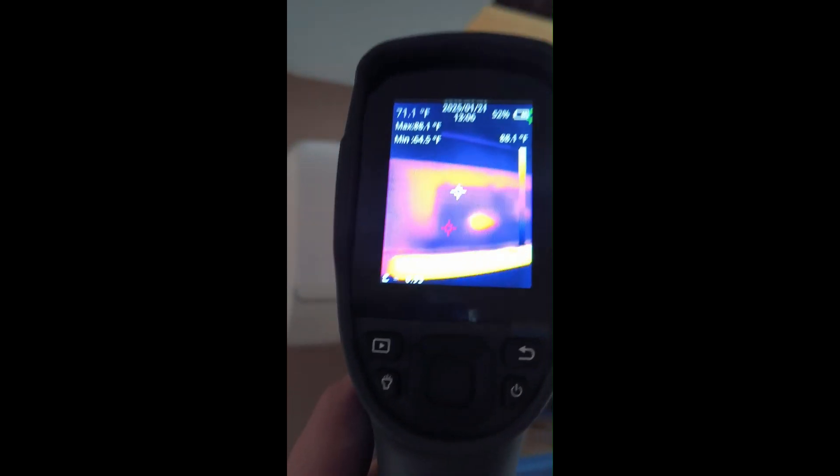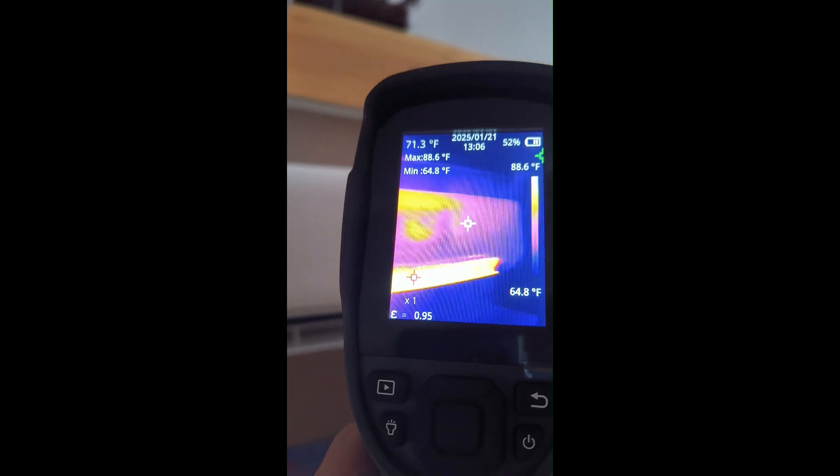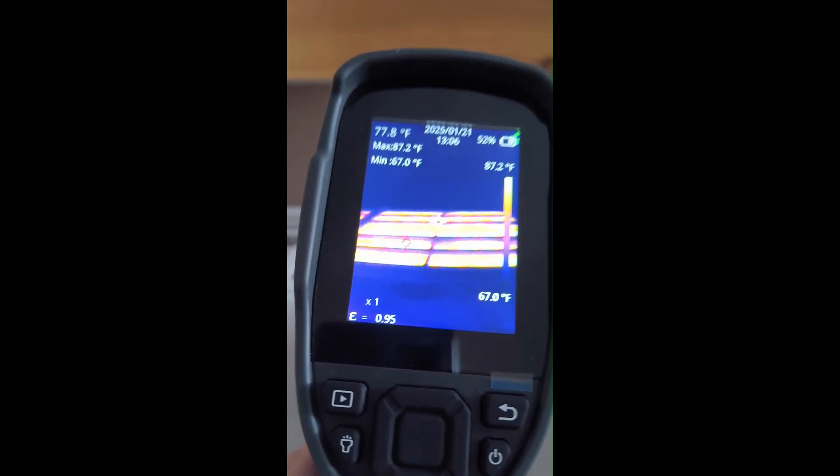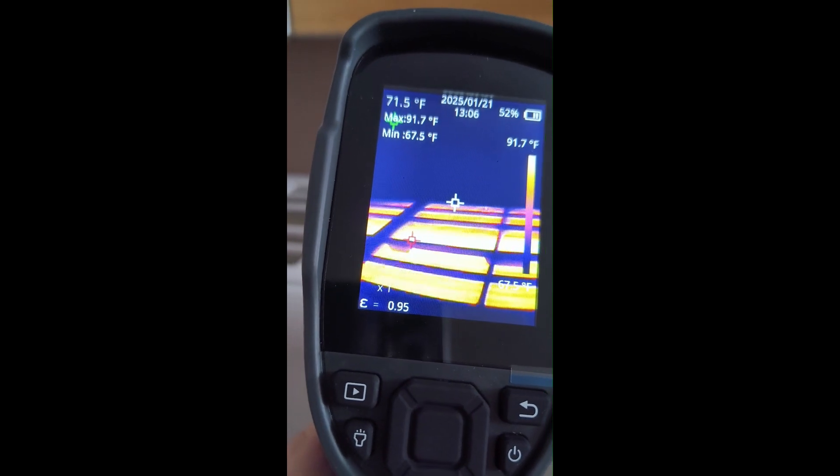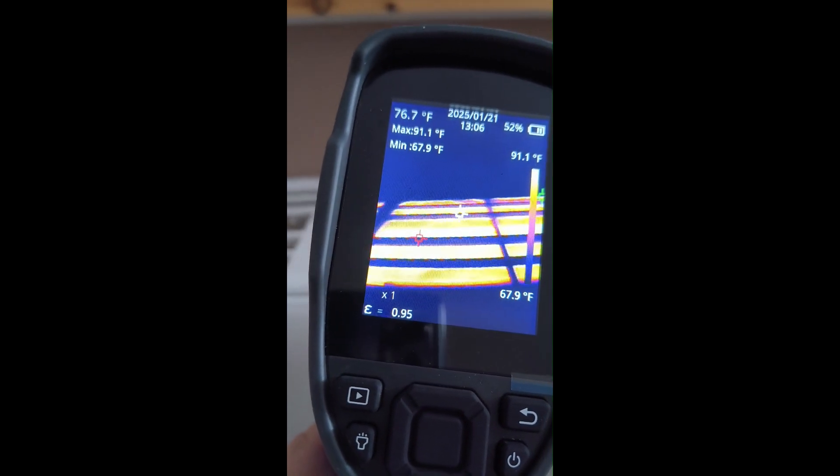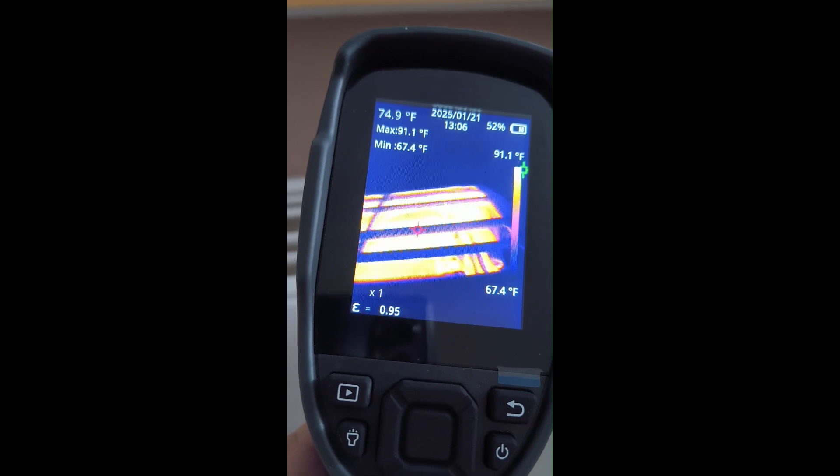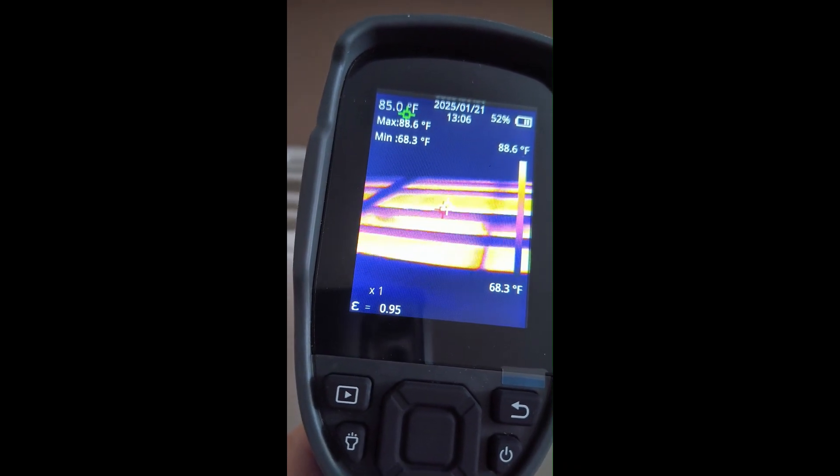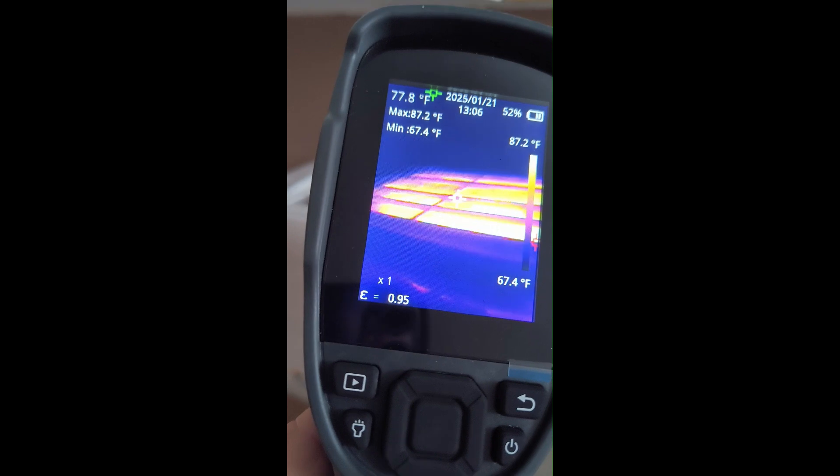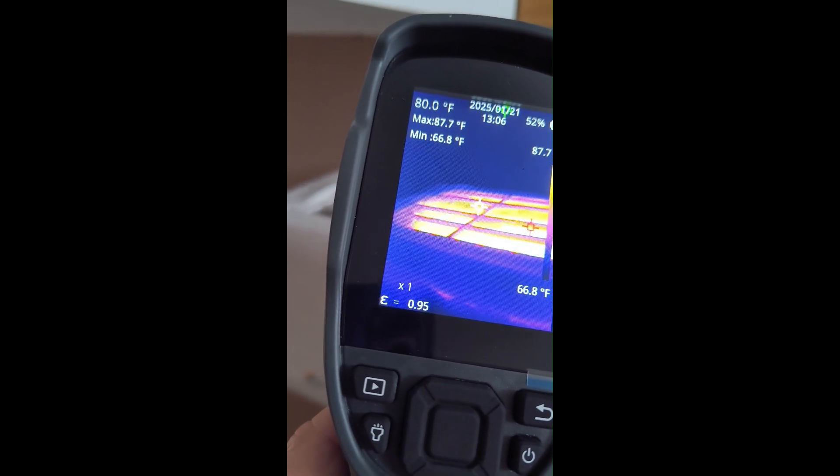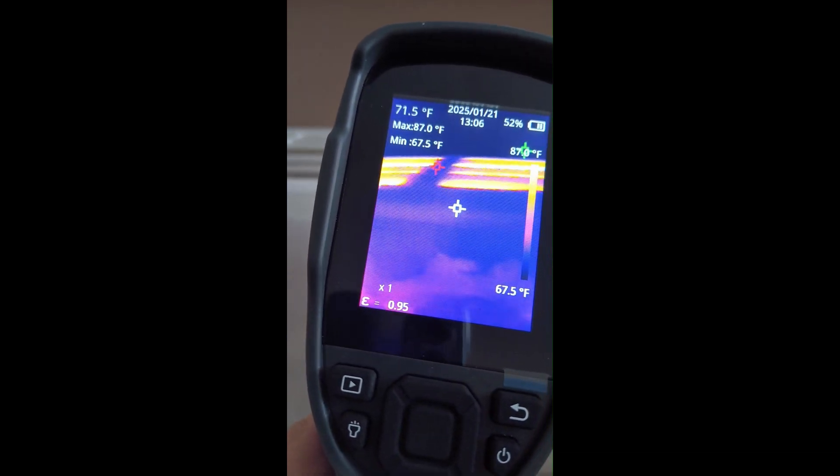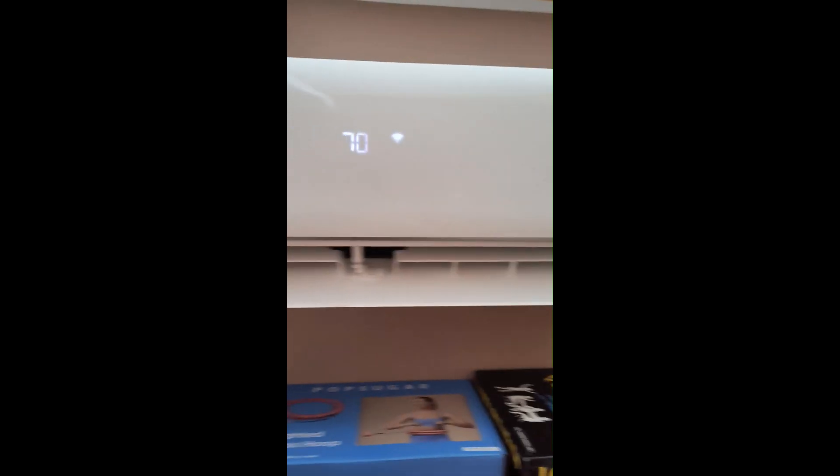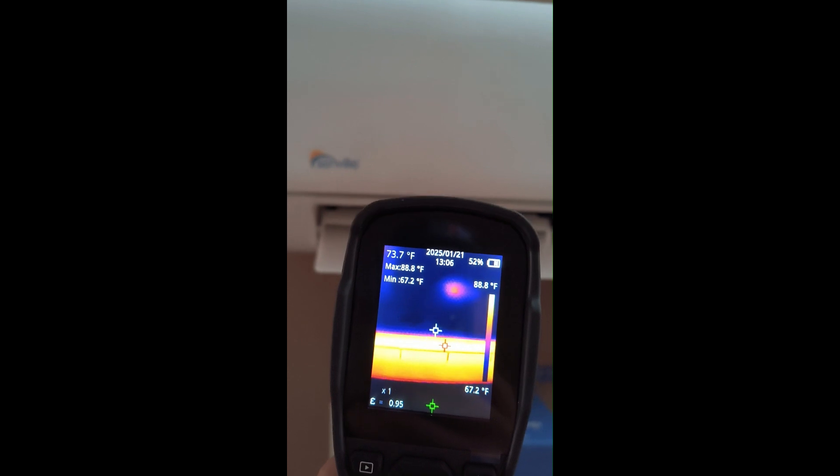But as we can see with this heat gun, even though it's at set point and it's done calling for heat, it's still got all this residual heat in the coil. So if the fan were going to keep running there, even if the fan was just at that minimum speed, this room, especially if it's a small upstairs bedroom, it's just going to keep getting warmer in here.